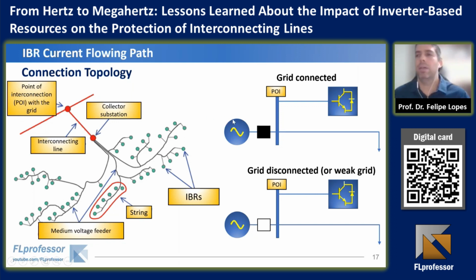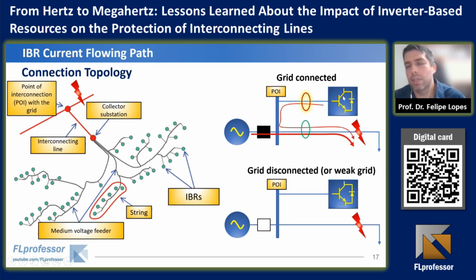And there are some very illustrative scenarios that I can comment on here. The first one is that when a fault takes place outside the protected line, for instance, let us assume that this line here is the protected line. It can have problems because through this line in this case, only the IBR contribution will pass through it. But in these adjacent lines here, if there is a grid contribution which superposes the IBR contribution, then the grid is usually stronger than the IBR most times.